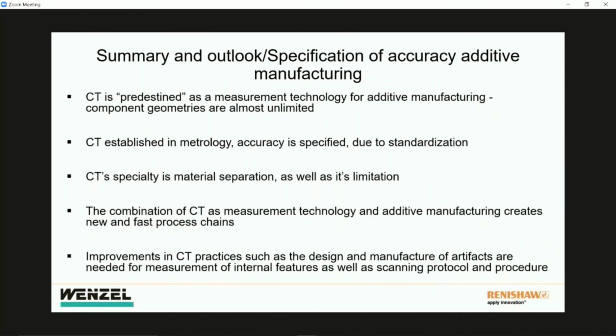CT is already standardized in terms of accuracy. That means we have guidelines we just follow to determine the accuracy. I showed you the slide with the tactile calibrated artifact. Concerning the material, is it a good thing or a bad thing? We have the possibility to resolve different kinds of materials by their density, as we can resolve inclusions by higher density, or a lack of material as pores when there is a lower density in a volume.